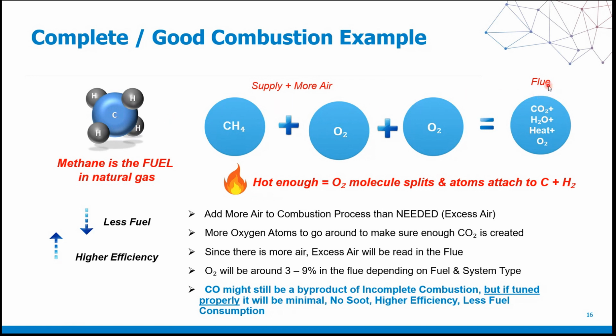So if we look at our flue here, our byproducts of combustion have changed, and we're in a much better condition. We're producing CO2, we're producing water, producing heat, we're producing oxygen. Those are byproducts of combustion that we want. Those are going to keep us out of the woods, so to speak, and out of trouble. So that's why it's very important that we understand incomplete combustion and its correlation and gateway to getting us to complete or good combustion.